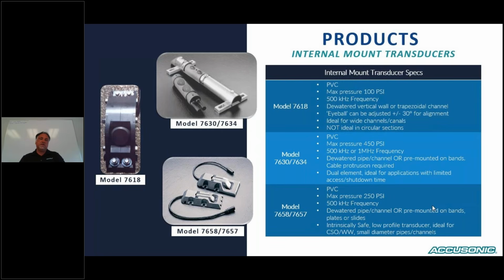It has a dual element. So there's basically two transducer faces built into each transducer, and it just has a little bit of redundancy. So if a customer can't dewater a penstock very frequently, they'll typically go with this style transducer. Each transducer body has two cables coming off of it. Those are good to 450 psi, and the utilization of a primary element and a backup element helps. If a transducer weakens over time, you can switch the elements at the electronics console.